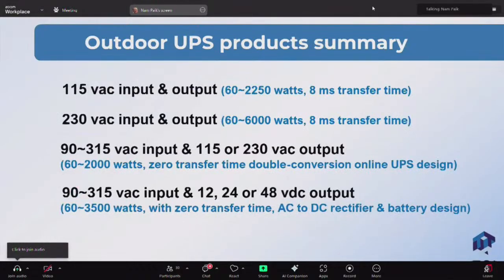Now I'll cover our outdoor UPS products. We make single-phase input and output outdoor UPS — uninterruptible power supply — products, with wide input range, 115 or 230 volt output, or wide input range plus/minus with DC output. If voltage in Africa is so unstable, you may need this type, which works over a plus/minus 12% range. This series is less expensive, but the double conversion topology gives a much wider operating input range with zero transfer.